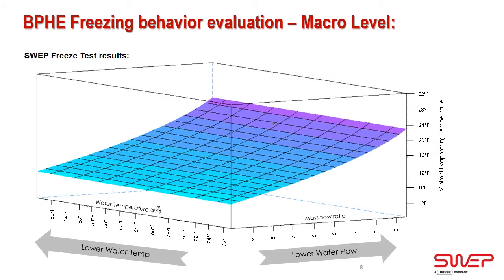The wall temperature or surface temperature is a good parameter to evaluate the risk of freezing. But unfortunately we can't measure it continuously and all over the heat exchanger. So we developed a method to define the freezing temperature of a brazed plate heat exchanger at specific conditions. By combining the test results of a couple of test points, we are able to develop this three-dimensional graph where on one axis you can see the water temperature, on the second one the mass flow ratio, and on the third axis the minimal evaporating temperature.